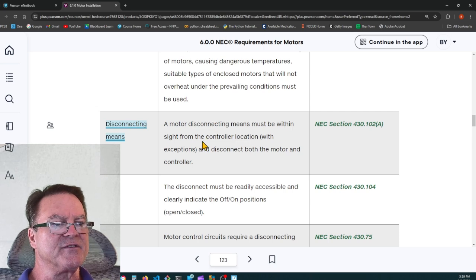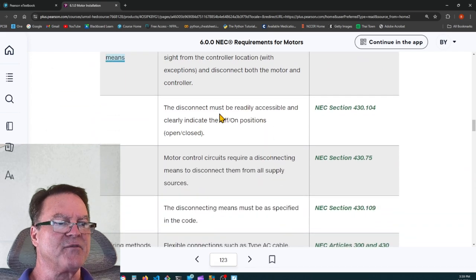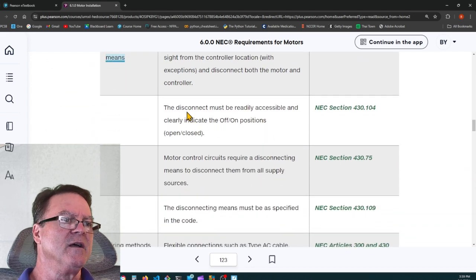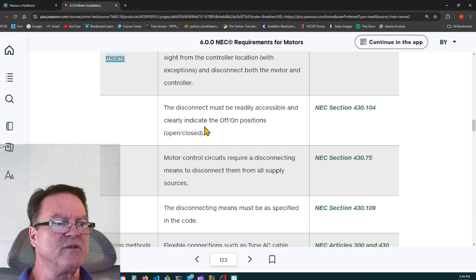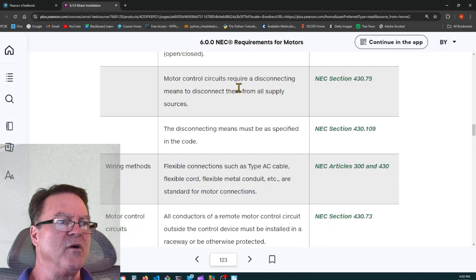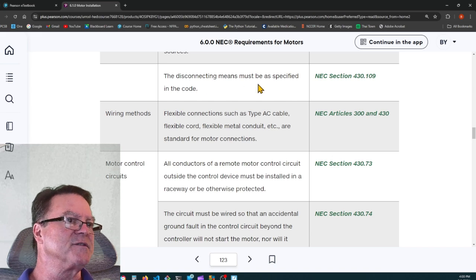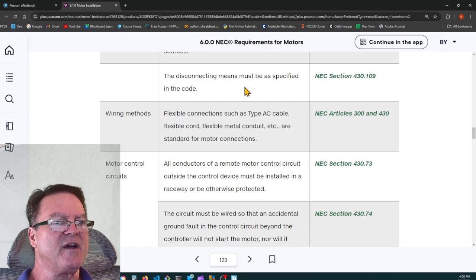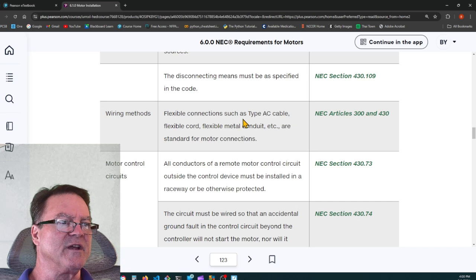Within sight means you have a straight line of sight to it and you're within 50 feet and it's not through doors or windows. The disconnect must be readily accessible and clearly indicate the on-off position. Motor control circuits require disconnecting means to disconnect them from all supply sources. The disconnecting means must be as specified in the code. Flexible connections such as type AC cable, flexible cord, flexible metal conduit, etc. are standard for motor connections because they vibrate.